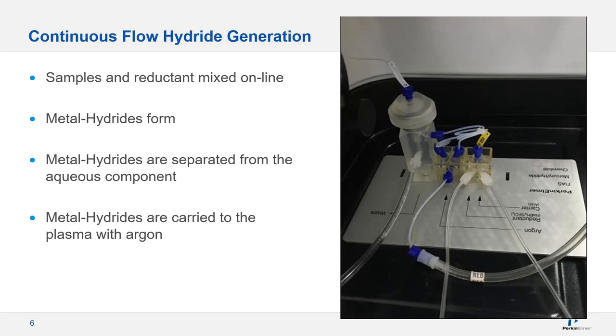Here's what the hydride formation system looks like in our instrument. The two lines on the right are where the reductant and sample come in and mix in the first mixing block. The hydride gas forms, and the nebulizer argon gas carries the hydride into the gas-liquid separator. The liquid is pumped out the bottom to drain while the hydride is carried to the plasma.